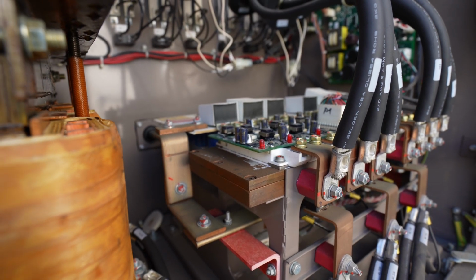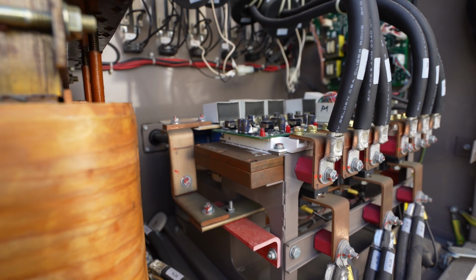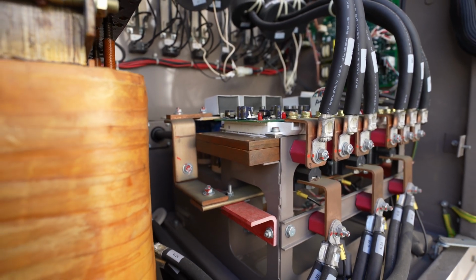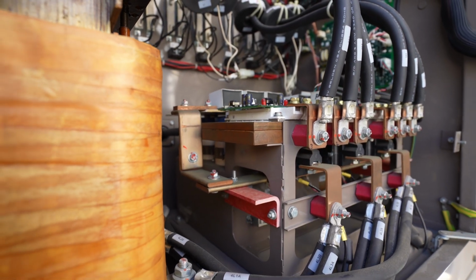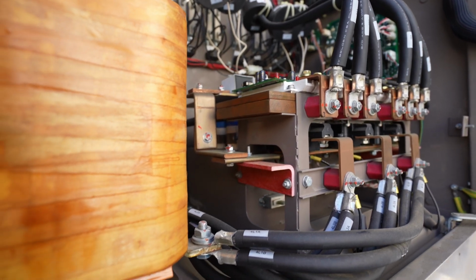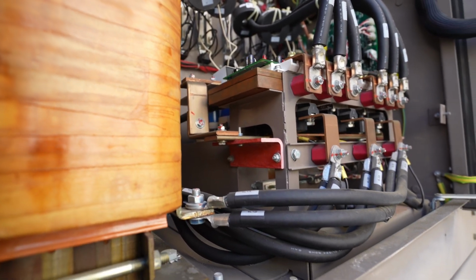So what we can do with that is we want to gently start the motor. If we just pull the contacts directly in, well, that's a lot of starting current. These SCRs have the ability to open and close very quickly, but we can do it in such a way to where we just momentarily give that motor bumps.